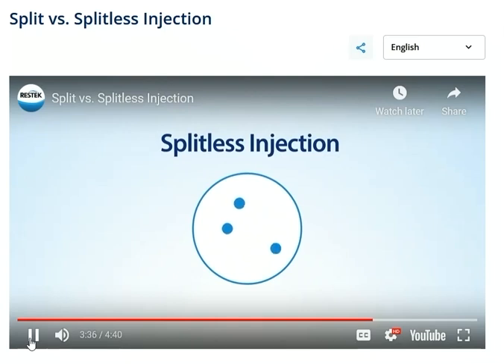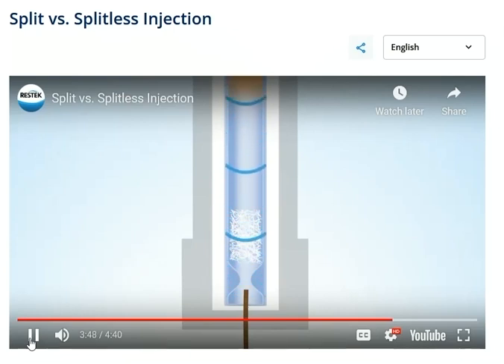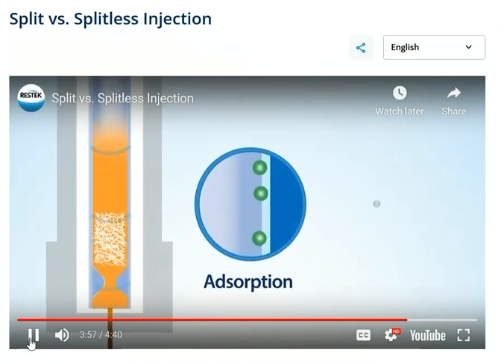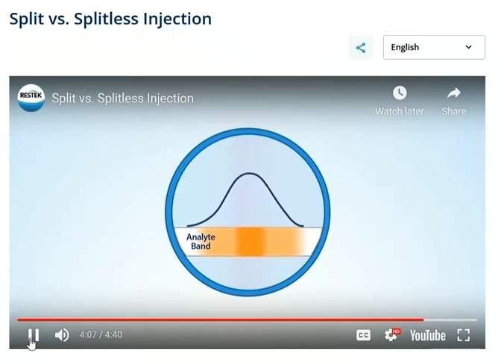But if your analyte concentration is very low, you may need to perform a splitless injection. Splitless injections excel at trace analyses. Since all the flow is directed to the column, you can transfer the majority of your sample. However, the slower flow rate into the column can result in the degradation of active analytes through adsorption and breakdown. It also leads to increased diffusion, causing band broadening — especially noticeable for more volatile analytes, resulting in wider peaks.